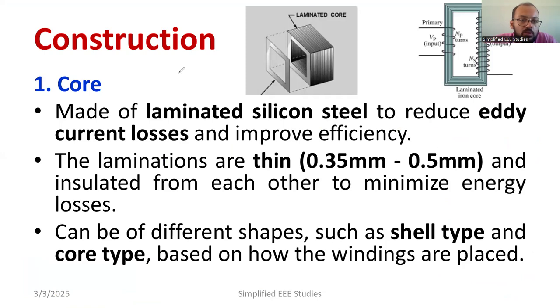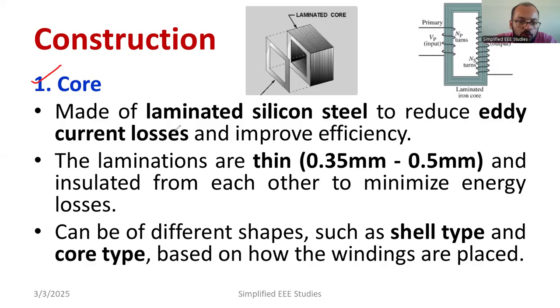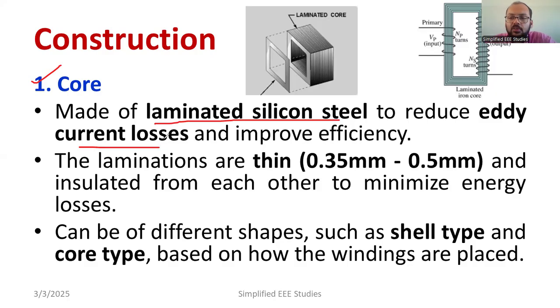First, I would like to discuss the transformer core. The transformer core ensures the movement of magnetic flux. Usually, the transformer core is made up of silicon steel. The main purpose is to minimize the eddy current loss. Apart from that, silicon steel has a very low value of hysteresis, so hysteresis loss will also be very low.